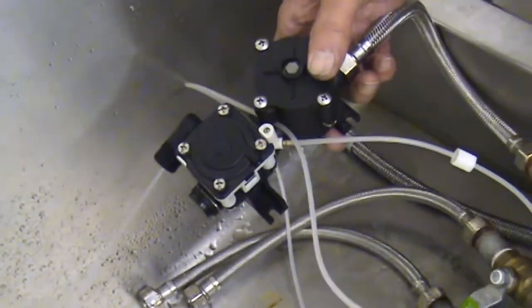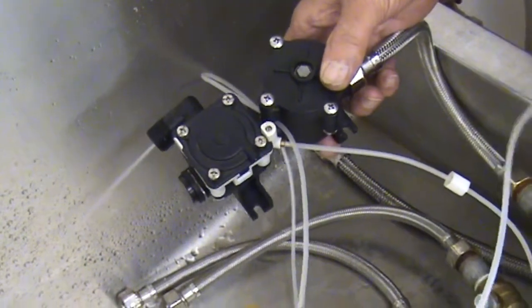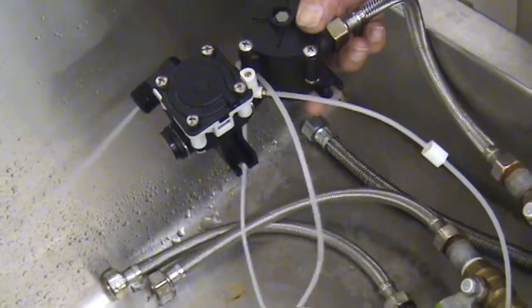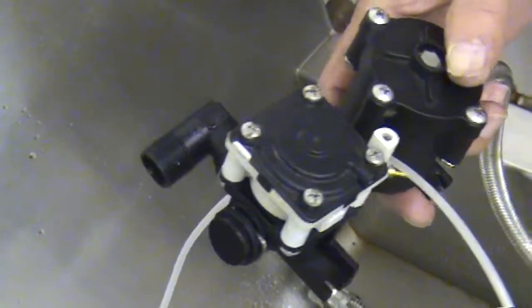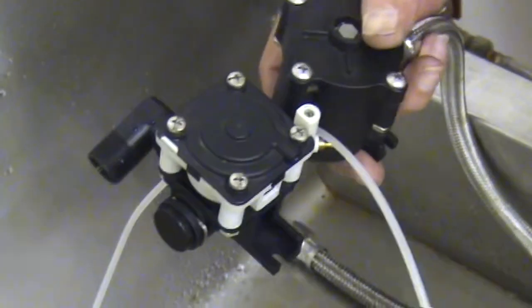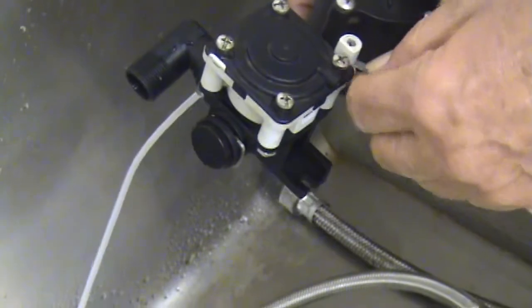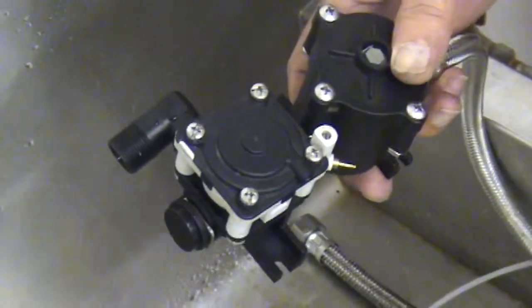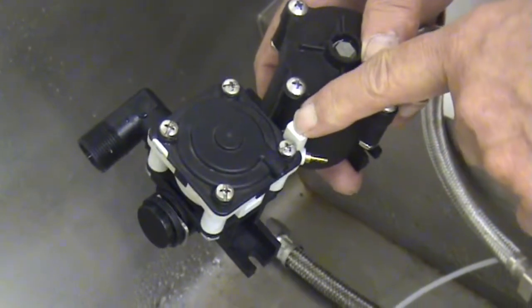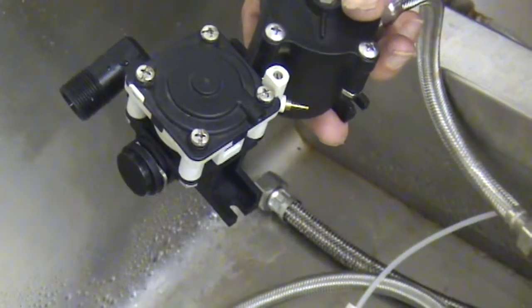Now the best way to determine if it's your valve or something else, is simply to disconnect your tubing from that input, and it should shut down pretty well within a few seconds. As you can see it did there. If it does that, you can be pretty sure that your timing is turned in too far and needs to be adjusted out.